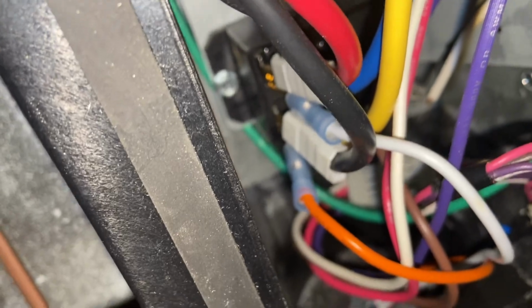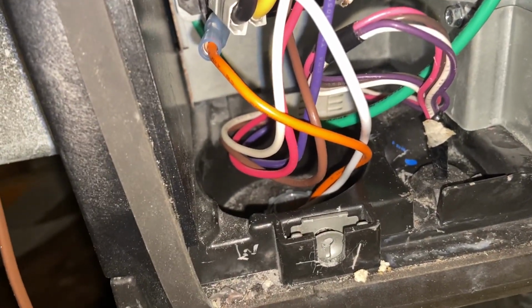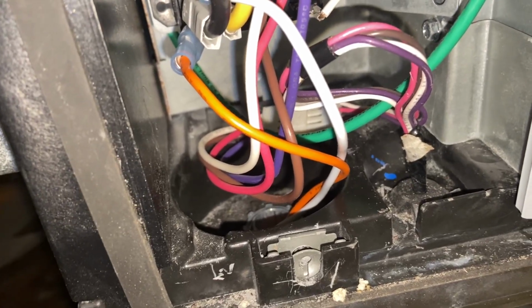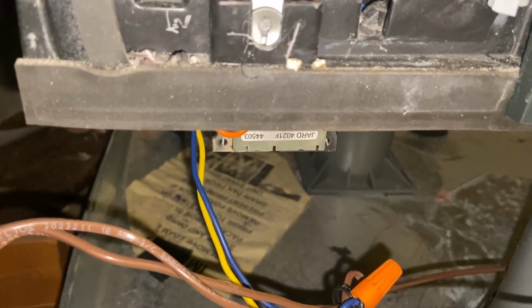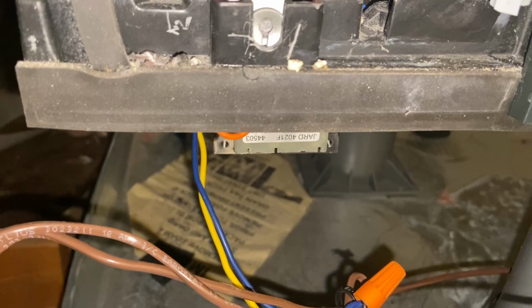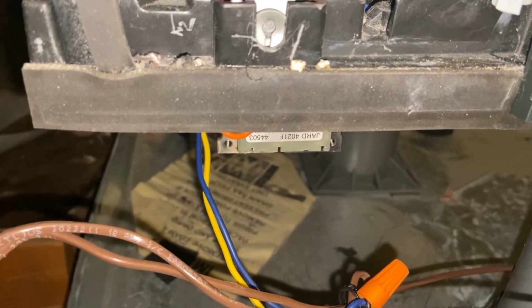Anyway, so I proceed to check the transformer. I start probing and pulling wires, etc. And what I found was that the transformer was getting 240 volts in, no problem, but it was not outputting the 24 volts. Okay, well, that seems to be the problem.